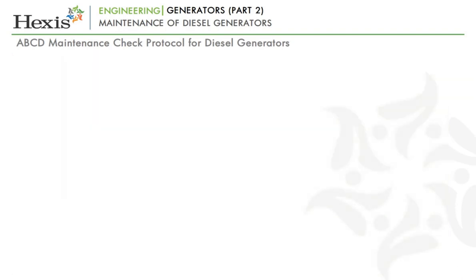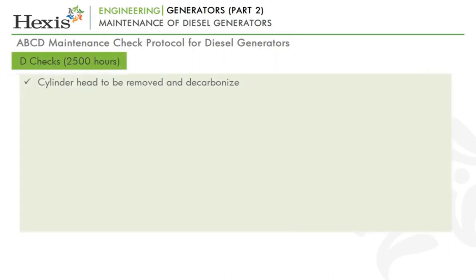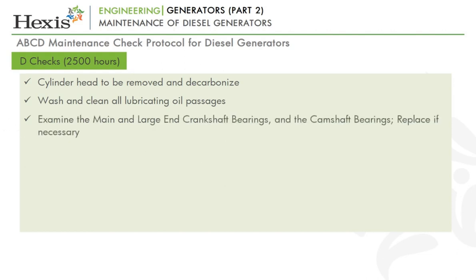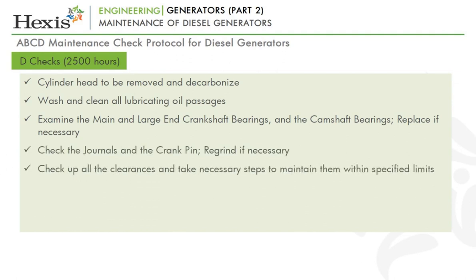The last type of checks are D-checks, which are conducted after 2500 hours of DG operation. Cylinder head to be removed and decarbonize. Wash and clean all lubricating oil passages. Examine the main and large end crankshaft bearings and the camshaft bearings. Replace if necessary. Check the journals and the crank pin. Regrind if necessary. Check up all the clearances and take necessary steps to maintain them within specified limits.